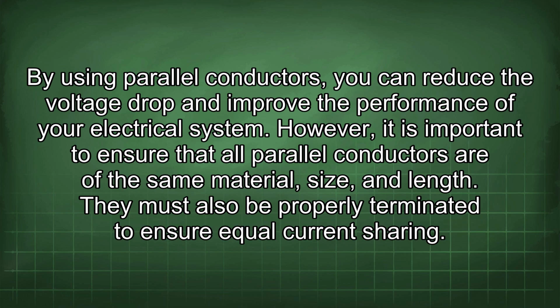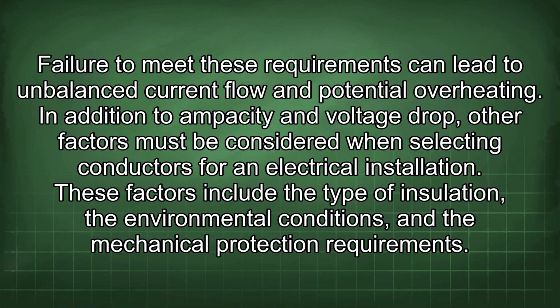By using parallel conductors, you can reduce the voltage drop and improve the performance of your electrical system. However, it is important to ensure that all parallel conductors are of the same material, size, and length. They must also be properly terminated to ensure equal current sharing. Failure to meet these requirements can lead to unbalanced current flow and potential overheating. In addition to ampacity and voltage drop, other factors must be considered when selecting conductors for an electrical installation. These factors include the type of insulation, the environmental conditions, and the mechanical protection requirements.